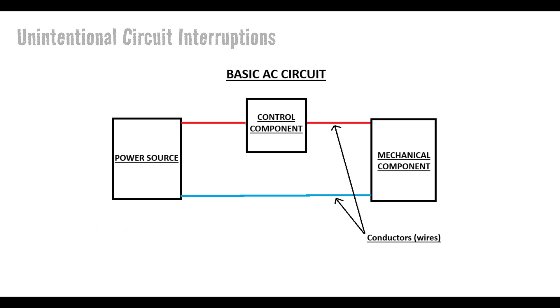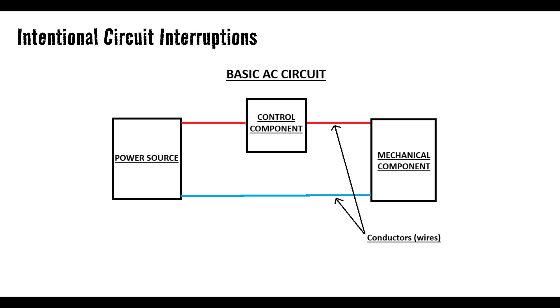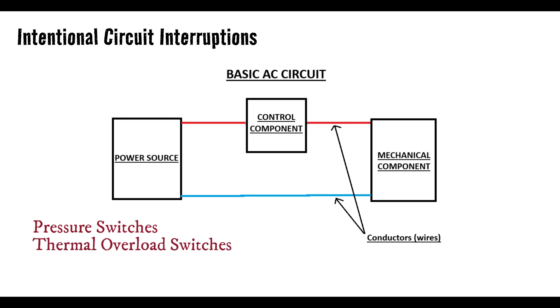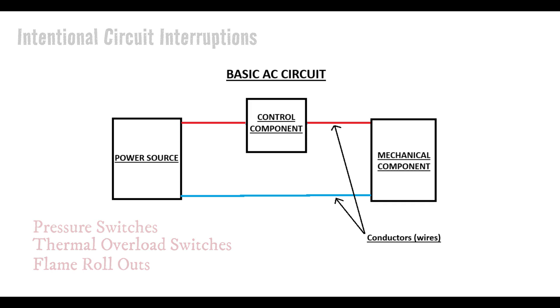You can also have intentional shutdowns of the circuit, where the problem has nothing to do with the circuit itself — it's actually external — but some safety device is wired into the circuit and designed to shut it down under those circumstances. We're talking about high or low pressure situations in your refrigerant lines, thermal overload switches that shut the circuit down on very high temperatures, flame rollouts. There's a variety of safety devices that will shut circuits down due to problems that have nothing to do with the circuit at all. But even those external problems can still be detected through the circuitry itself.